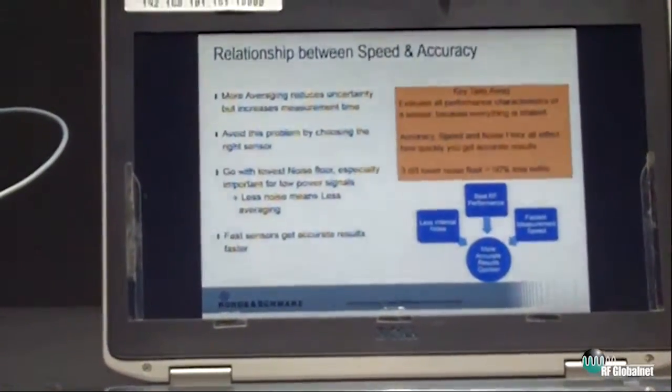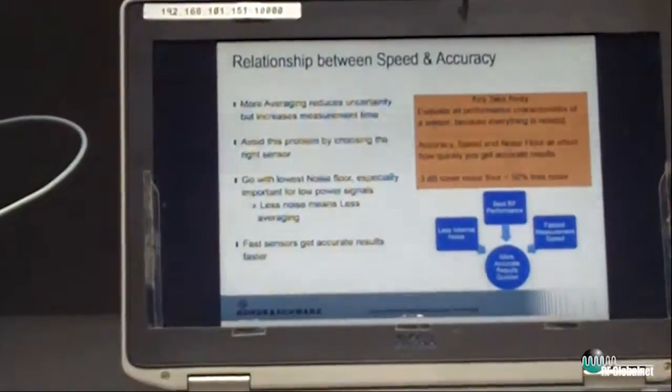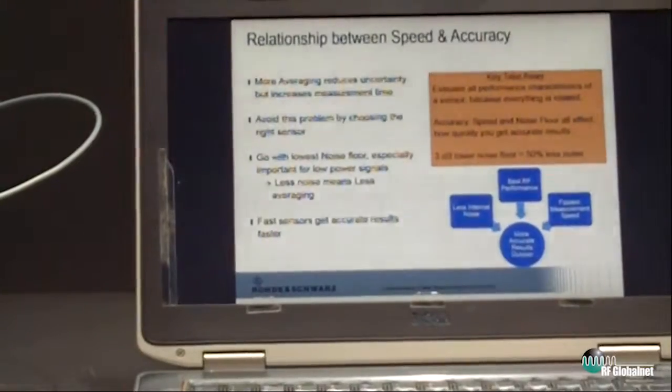These are big factors in determining how accurate you can make a measurement. A power sensor data sheet is very long and complex, so the rule of thumb I always give people is: look at the noise floor. Because the less noise you have in the sensor, the quicker you'll make an accurate measurement. To make any accurate measurement, you need to make a number of averages to get a reading — the more averages you make, the more time it takes. The more noise you have, the more averaging you need to do. So go with a sensor that can make fast measurements and has a low noise floor. When you have a low noise floor, you need to do less averaging, which means you're going to get those accurate results quicker.